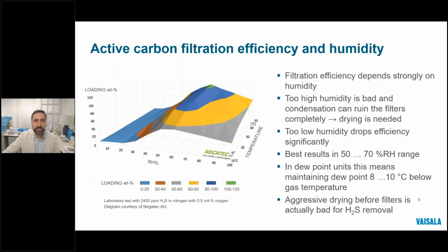A prime example of this is with the carbon filters used for H2S removal, which function optimally within a range of 50 to 70% RH, or at a dew point about 10 to 20 degrees Fahrenheit below the gas temperature. One of our European partners, Negatec, provided these test results for their filters and have begun recommending dew point measurement to their customers for these reasons. Too high humidity could damage the filter if it's allowed to condense and saturate, and too low will significantly decrease the effectiveness. And given the critical step of H2S removal, it's important that this part of the process is protected. Next.